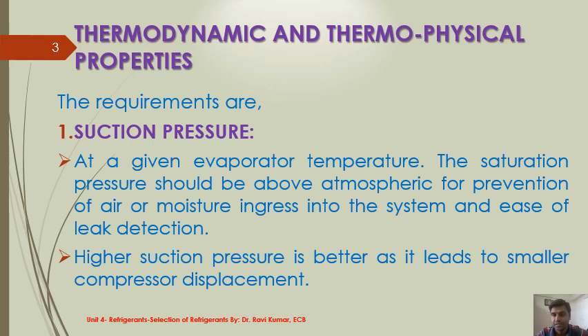Higher suction pressure is better as it leads to smaller compressor displacement. When suction pressure is higher at a given temperature, the density will be high and the specific volume will be low. That means for a given mass flow rate, the required size of the compressor will be small. So suction pressure should always be as high as possible. This is the first requirement for any ideal refrigerant.